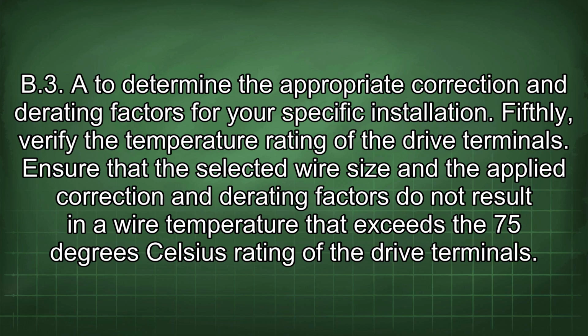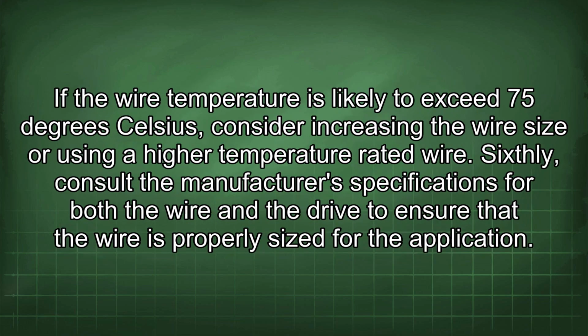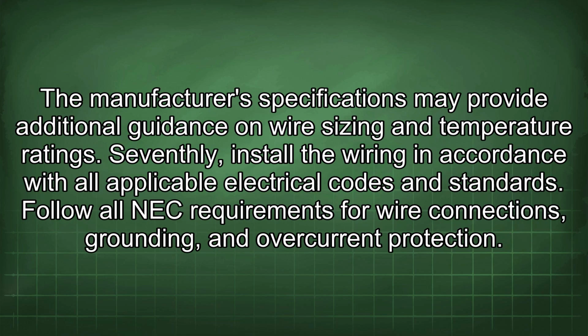Fifthly, verify the temperature rating of the drive terminals. Ensure that the selected wire size and the applied correction and derating factors do not result in a wire temperature that exceeds the 75 degrees Celsius rating of the drive terminals. If the wire temperature is likely to exceed 75 degrees Celsius, consider increasing the wire size or using a higher temperature rated wire. Sixthly, consult the manufacturer's specifications for both the wire and the drive to ensure that the wire is properly sized for the application. The manufacturer's specifications may provide additional guidance on wire sizing and temperature ratings.